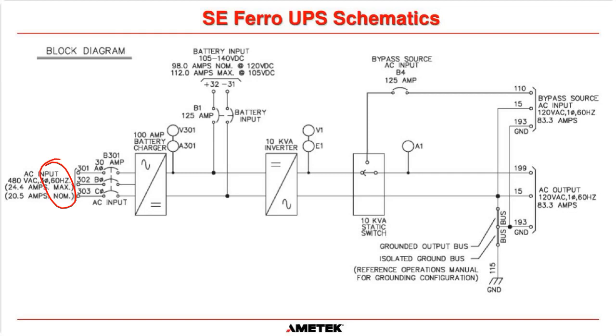So this line here, that delineates the outside of the UPS. So as soon as we go to the right-hand side of these terminals here, we are now inside the UPS. And terminals 301, 302, and 303, that's where you connect your AC input, your 3-phase cables. Then that goes through B301, which is our AC input breaker. That goes into our rectifier battery charger, which converts AC into DC.